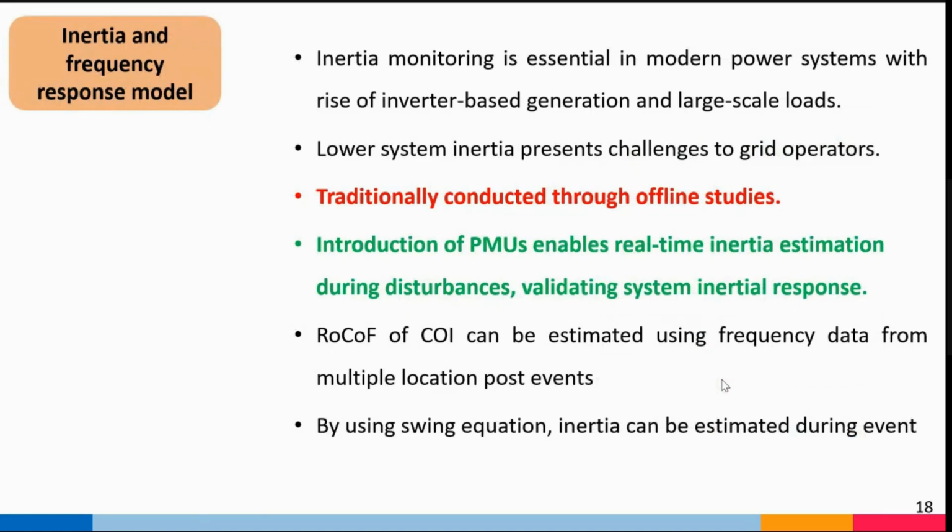The fourth one is the inertia and frequency response model. Inertia is also very important to monitor in the system because of the increase in inverter-based generation, and at larger scale, inverter-based loads are also increasing, the silicon loads as we usually call them, or loads which do not respond with respect to frequency. They are decoupled from the system.